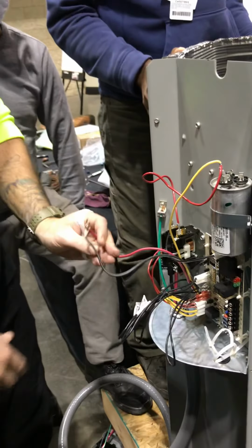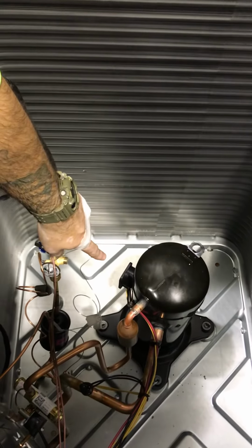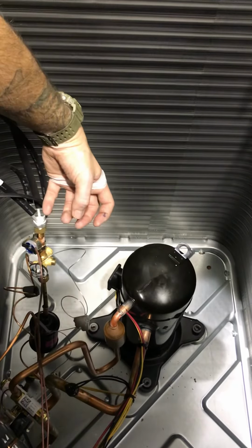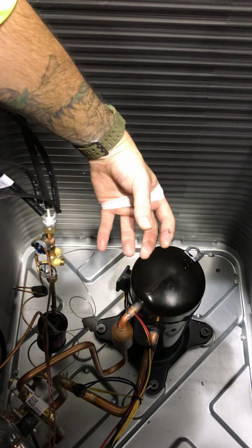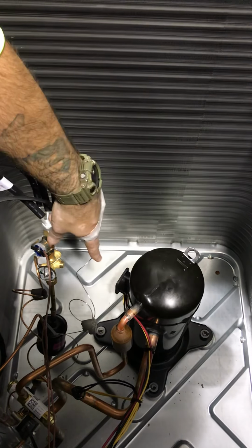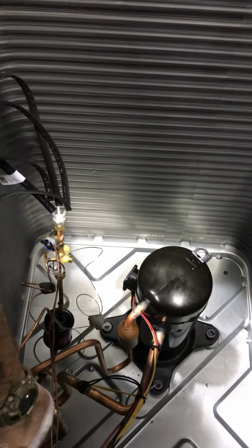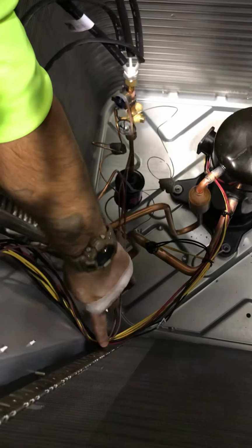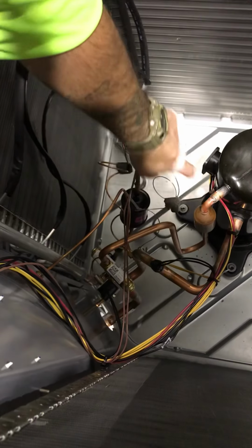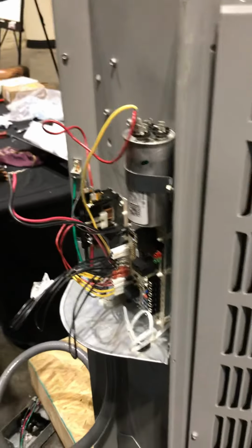Okay, and then I can follow these wires back to my box, which is right here. See that junction box? Remove that and see if that's burnt and corroded and rusty, so that's the problem. Or the wire's cut right here, maybe, and it's touching the condenser. Maybe that's the problem. But you just trace your wires back, and then that lets you know whether my compressor's tripping out or my compressor's not tripping out.